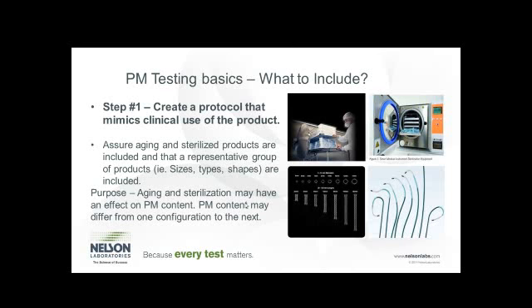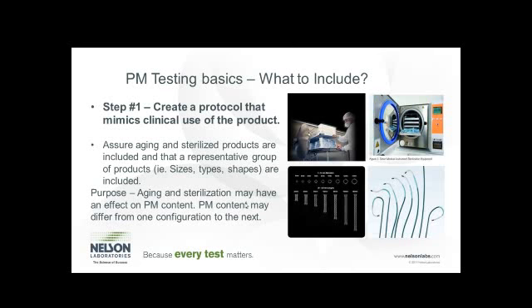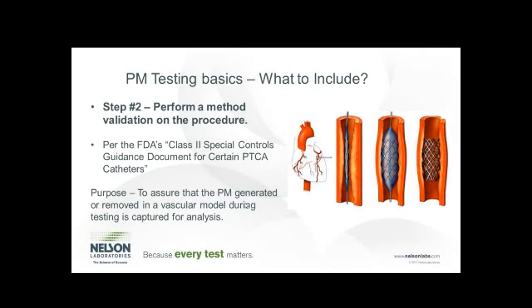The last part of step one is to assure that aging and sterilized products are included in the representative group of products that you'll be testing. Also, as a representative group, include different sizes, types, or shapes of your device. We recommend including different sizes — not just a worst-case scenario, but also maybe the smallest, somewhere in the medium, and the largest, if that applies to your device. The purpose of this is that aging and sterilization may have an effect on particulate matter content. We have definitely had sponsors whose submissions were kicked back for not including the variety of devices in their test scheme.